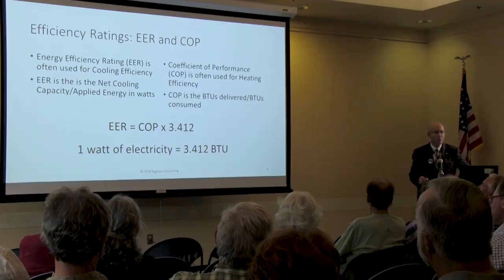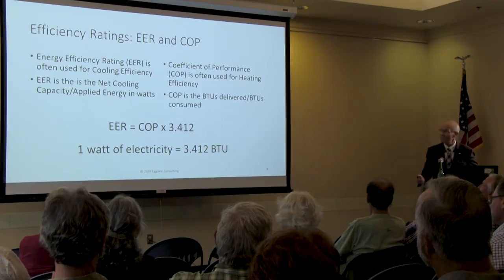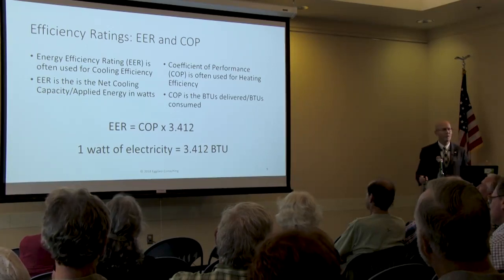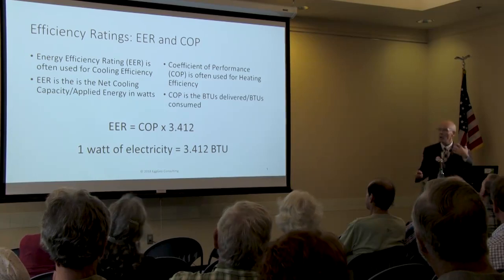Now, the U.S., interestingly enough, is the only one that tries to confuse the issue by using an energy efficiency rating. Heat pumps in the rest of the world are rated in COP both for heating and cooling. You're familiar with that. And so COP is super simple, because if I tell you I have a heat pump with a COP of 5, that means for every unit of electricity it's using, it's delivering 5 units of heat, the equivalent of 5 kW. So if it's using 1 kW of electricity and it's a 5 COP, it's going to deliver 5 kW of heat.